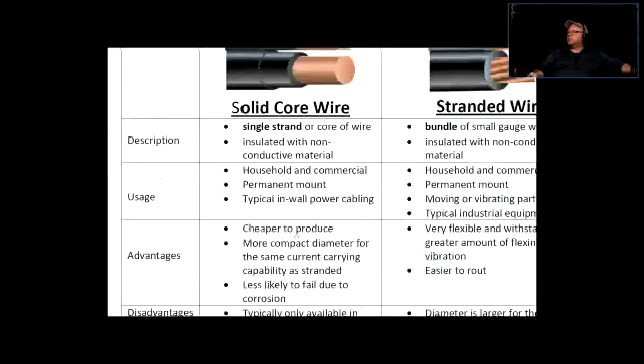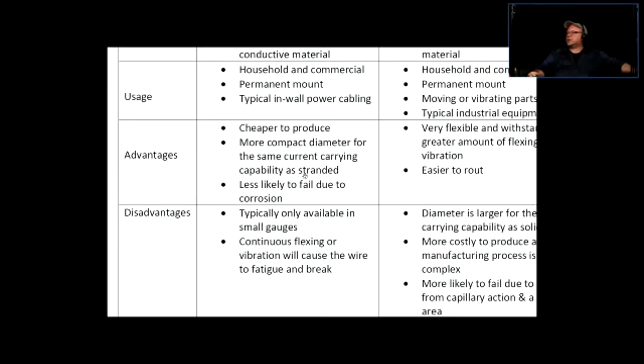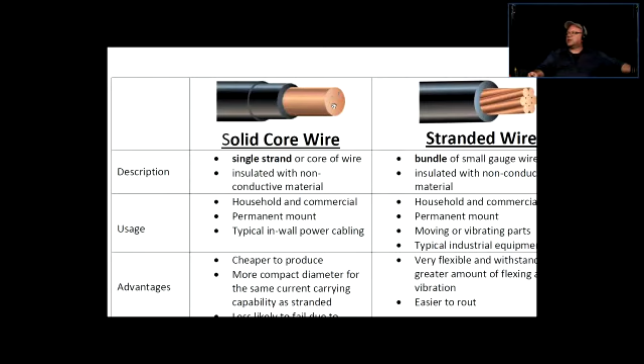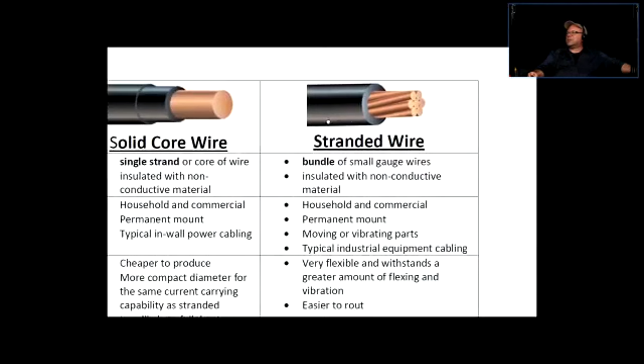It is less expensive to produce the solid wire, and it has a more compact diameter for the same current carrying capacity as stranded. Since it's one solid piece carrying the same gauge or current capacity, it's more compact and physically takes less space. For the same gauge or current carrying capacity in stranded, you still have the same amount of copper, but it's a bunch of smaller gauge wires bound together, so physically this whole thing takes more space.